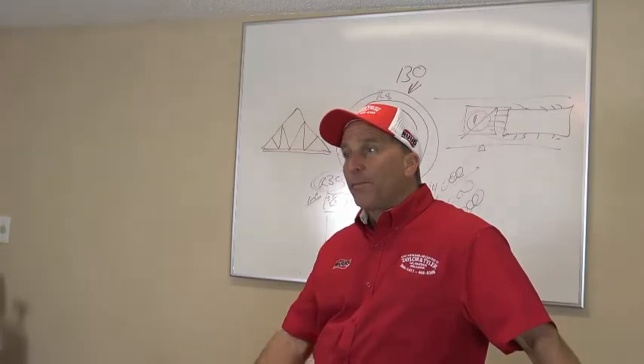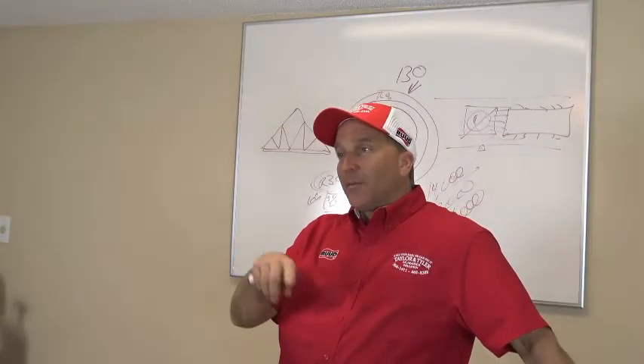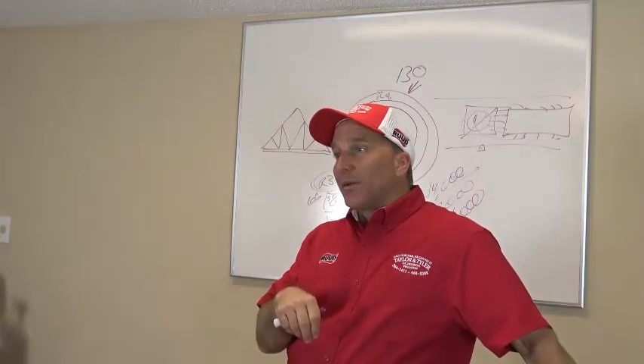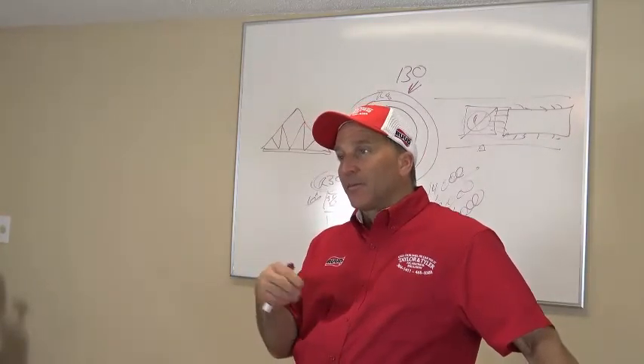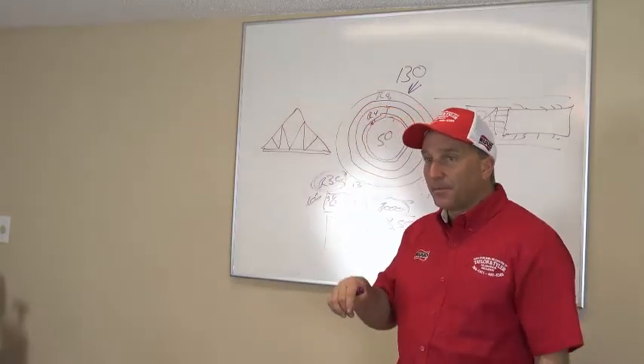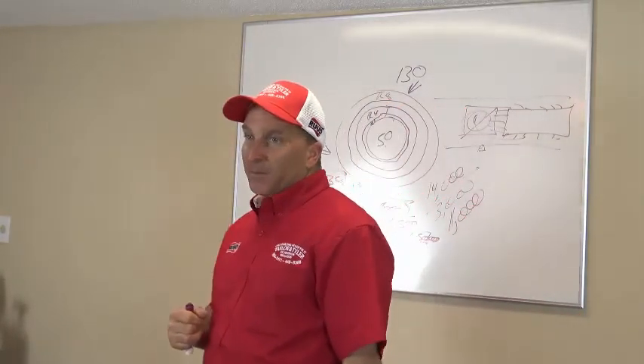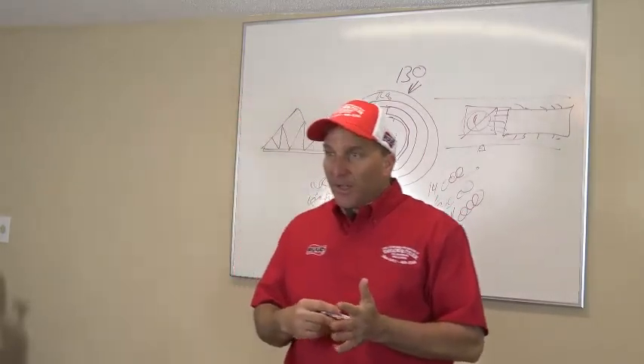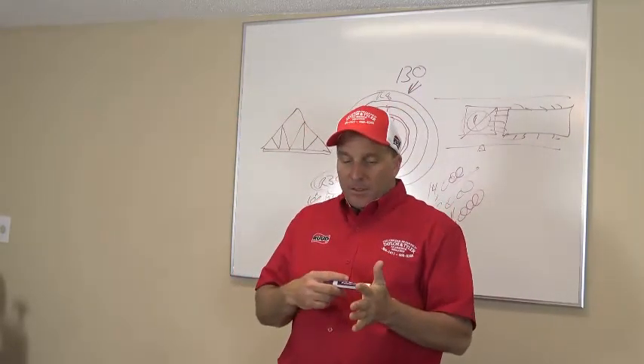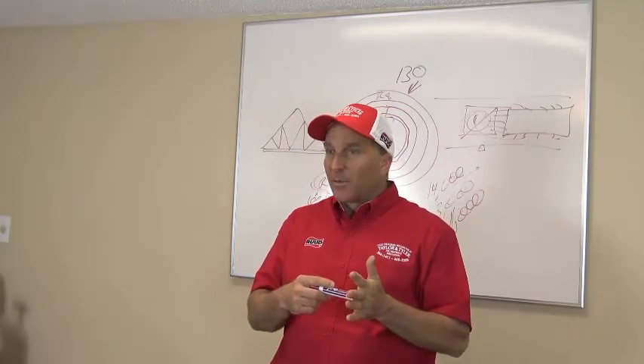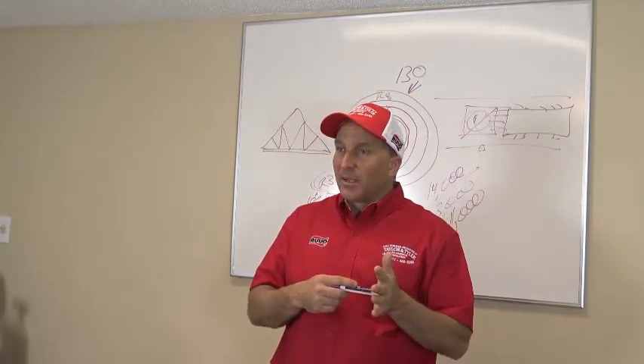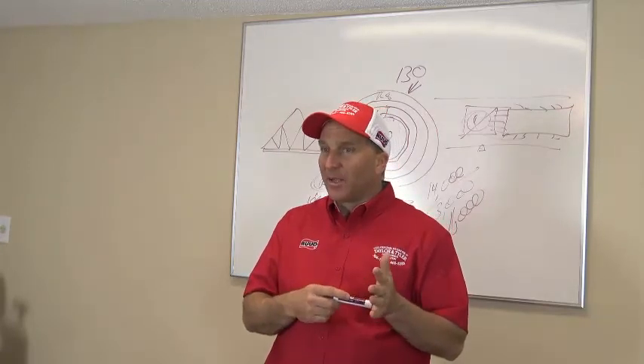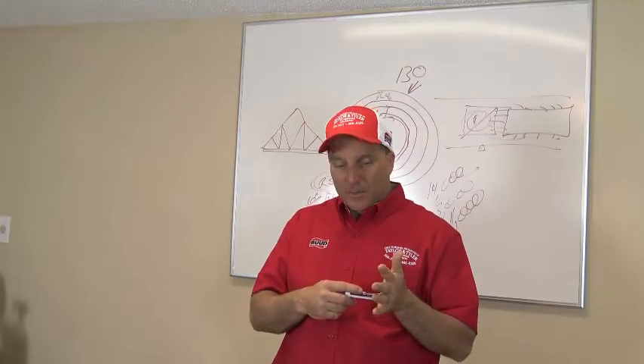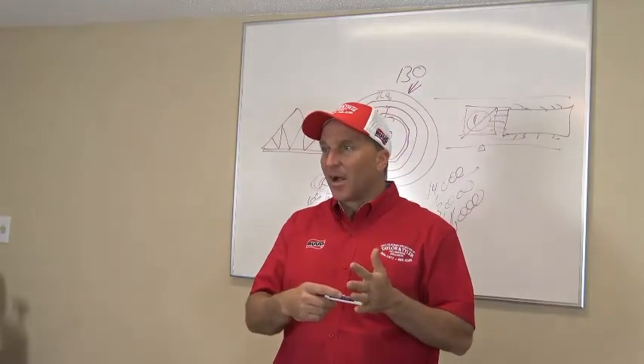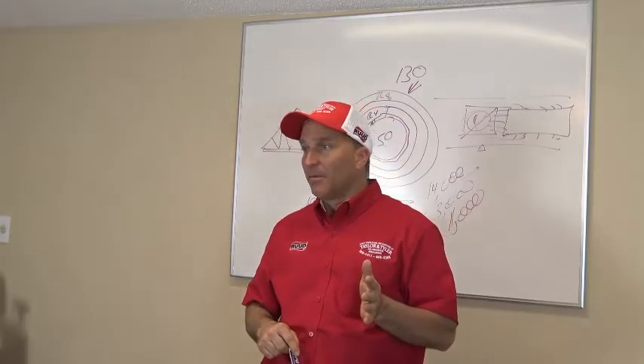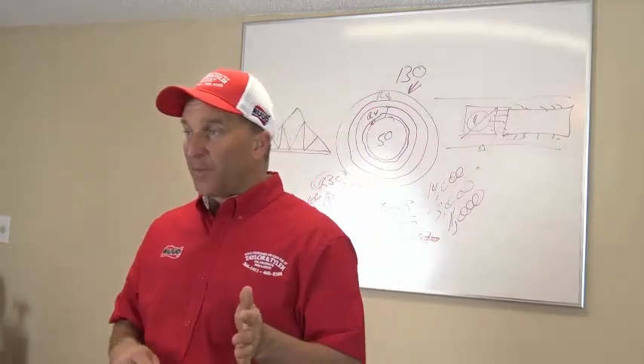Right? Next time you go out there, you look at the documents you saw last time, you made those recommendations, now you can make the same recommendations. True story, went out to a guy's house. Blew his drain lines out. I wrote honest recommendations. System is installed wrong, drain lines are backing up, all the drain lines need to be replaced, the evaporator coil is rusting out, needs to be replaced, customer needs a new system. Customer does not want to replace the system at this time. Customer signed it. Okay? They paid me for the service fee and they paid me for blowing drain lines.